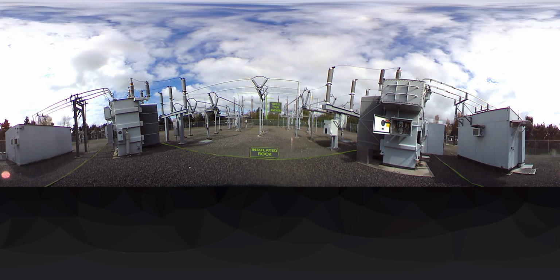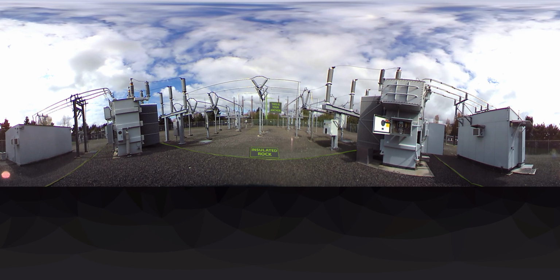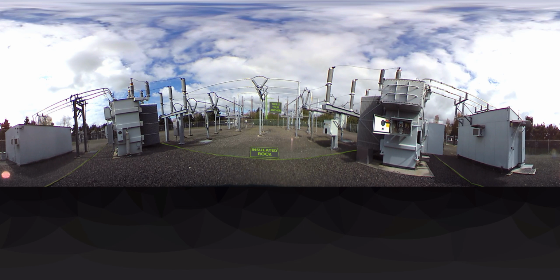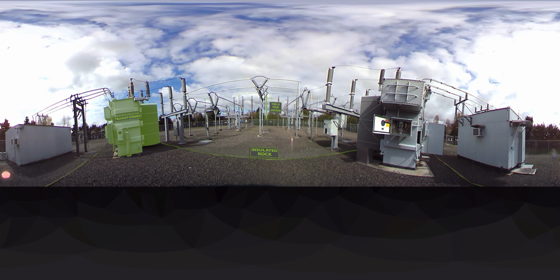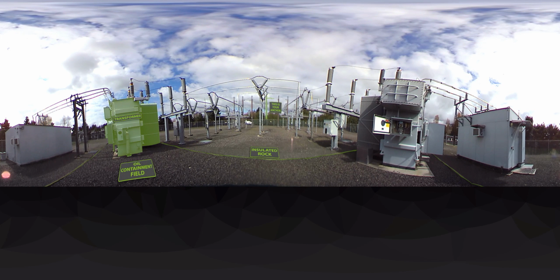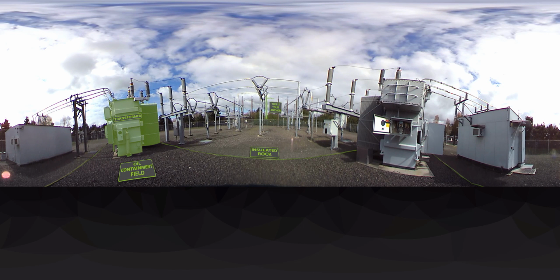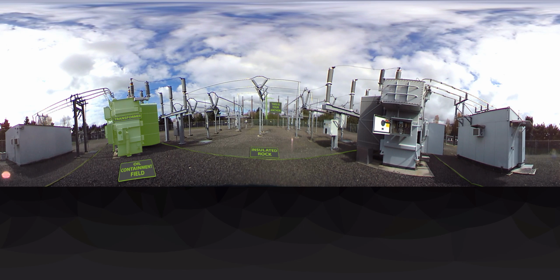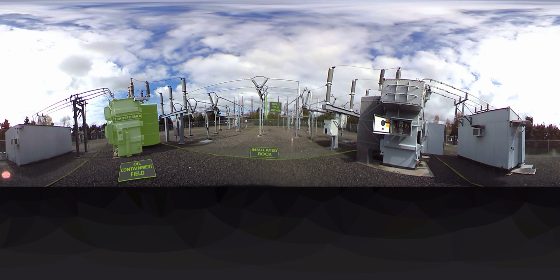Now, as you continue to look at the ground, you can quite clearly make out a transition within the rocks from the lighter colored insulated rock in the background to the darker rock in the foreground. If you spin your camera to the left and stop when you have the transformer in the center of your screen, you can clearly make out the difference even more. This darker area of rock that the transformer sits on is for oil containment. This is here to safeguard against the possibility of a catastrophic failure in which all the mineral oil would leak out of the transformer. To mitigate such a failure, this barrier of rock is about 4 or 5 feet deep, lined on all sides, and acts like a pool for the oil to drain. This would prevent the oil from causing any environmental problems in the soil surrounding the station.